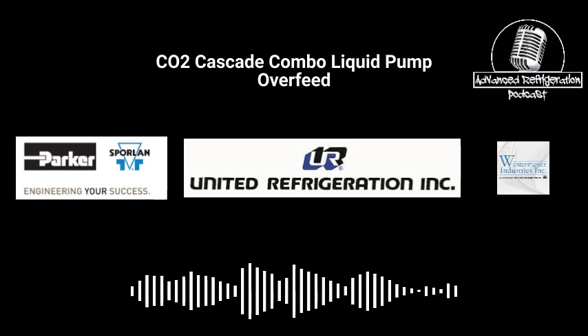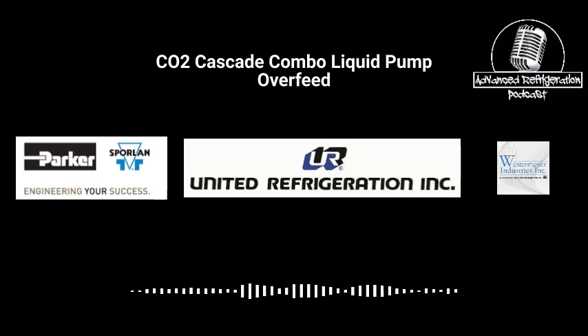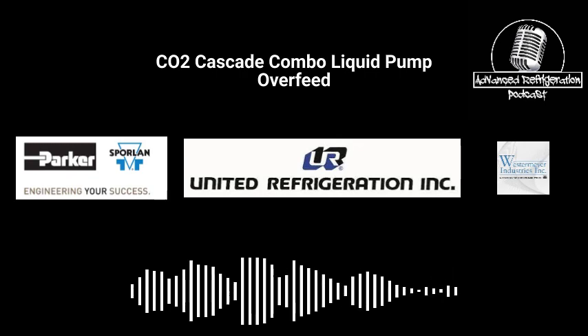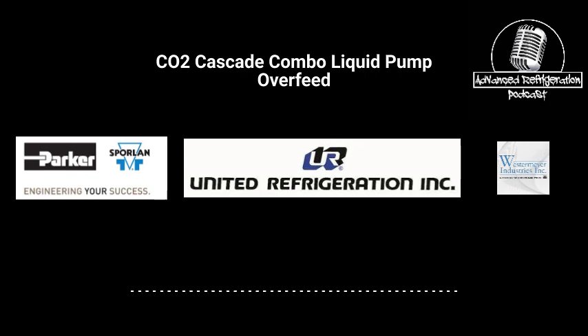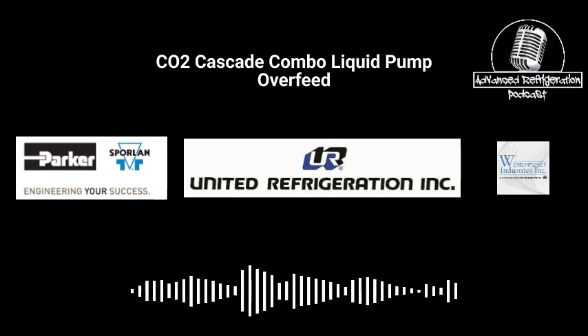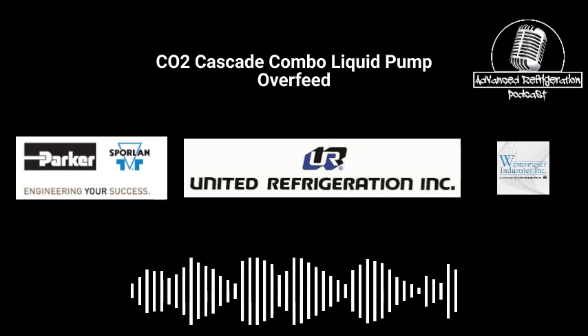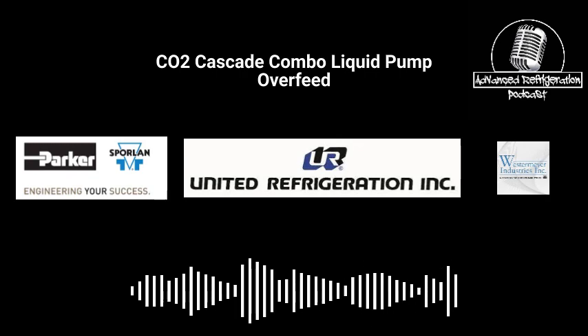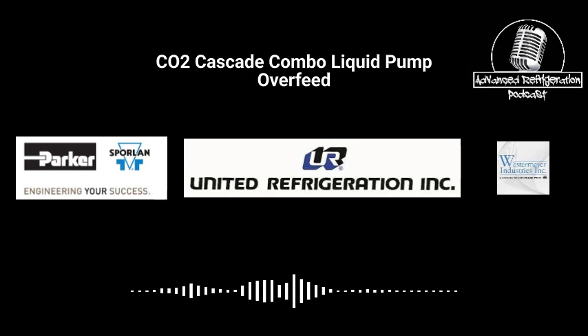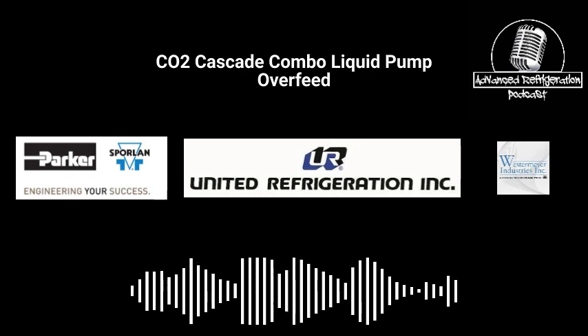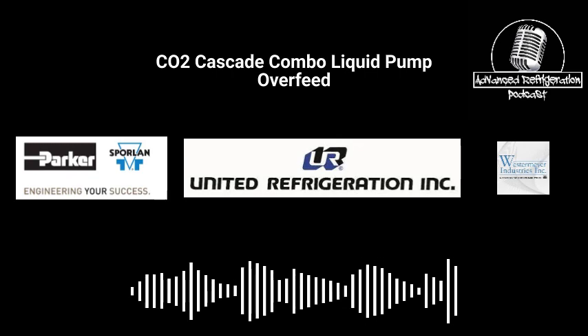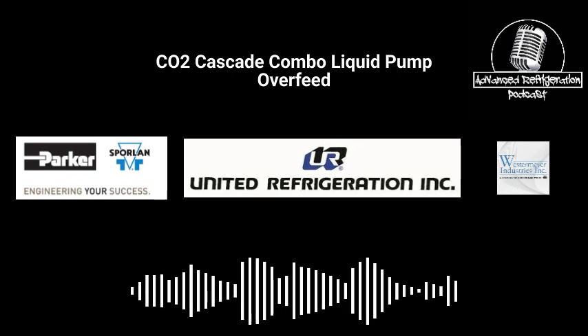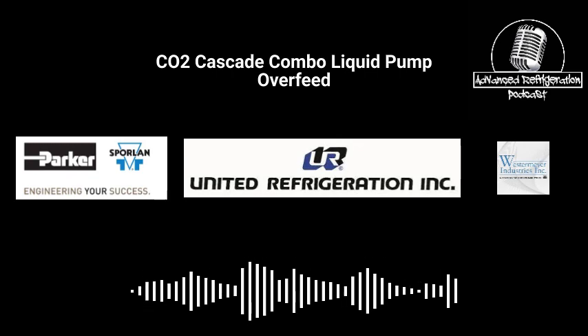So there is no discharge pressure in the subcritical, or if the subcritical compressor is going to be, we'll say, like 400 pounds. Well, that's what I'm saying. The saturated is that low. How are you going to get any heat exchange? It's all about discharge superheat. They call it latent. It's basically latent gas below freezing defrost. That's how all the CO2 racks are at Costco. So they run a latent. They run hot gas defrost off the low temp compressors.